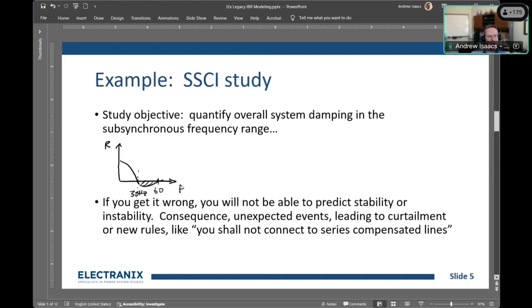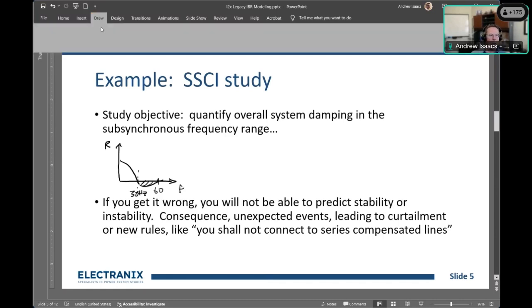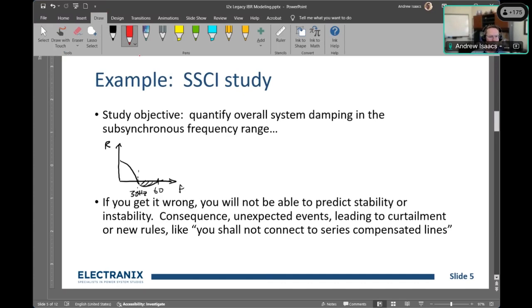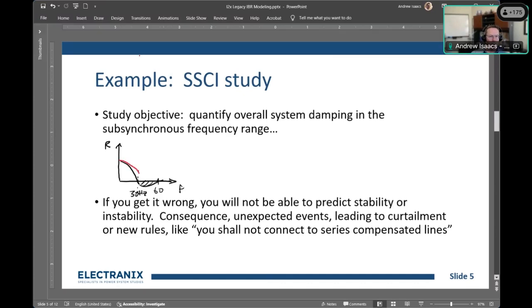Now suppose the frequency scan, instead of crossing where it did, crossed at maybe 35 hertz instead. This difference of 3 to 5 hertz in an SSCI study in Texas can be extremely important—it can be the difference between a successful project and an unsuccessful one.